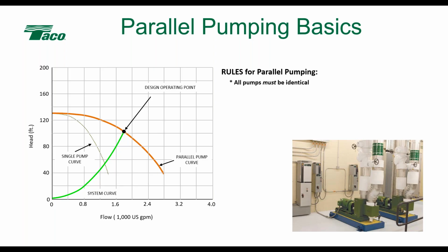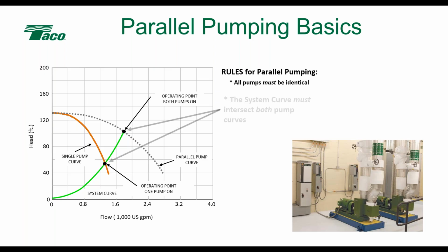So our parallel pumps have to be identical, okay? Each pump is operating at its own half flow rate on its own individual curve. But what we have to understand is that the motor has to be sized for when a single pump comes out and crosses the system curve. So we've got to make sure the motors are sized for that operating point with one pump on. Otherwise, we get into a motor overload condition.